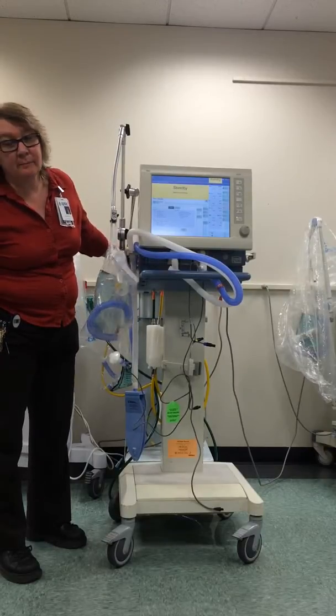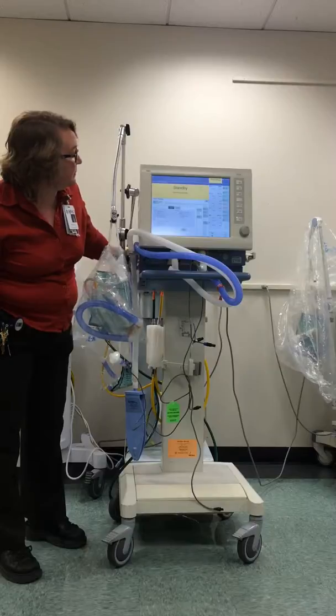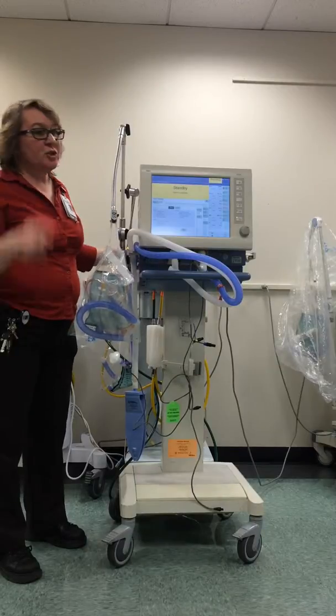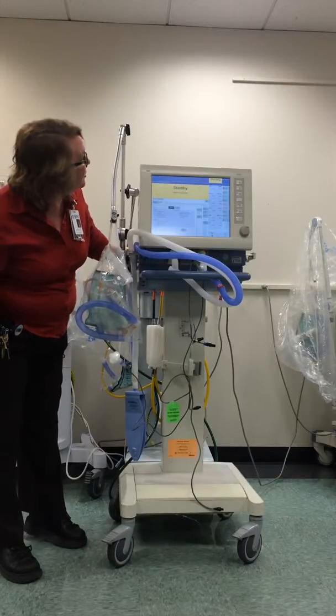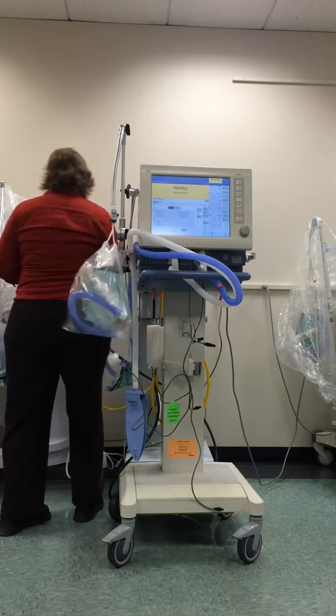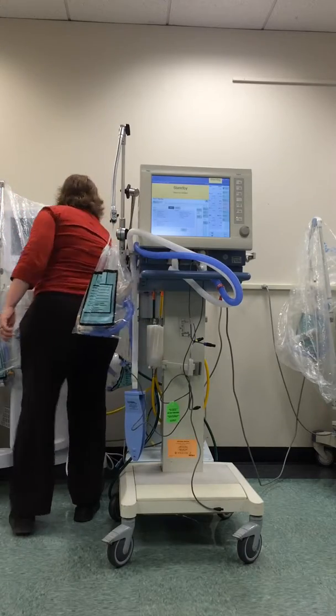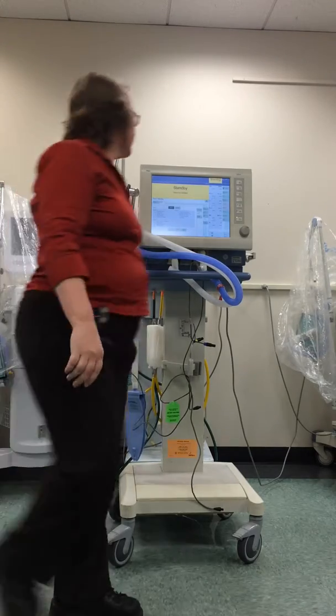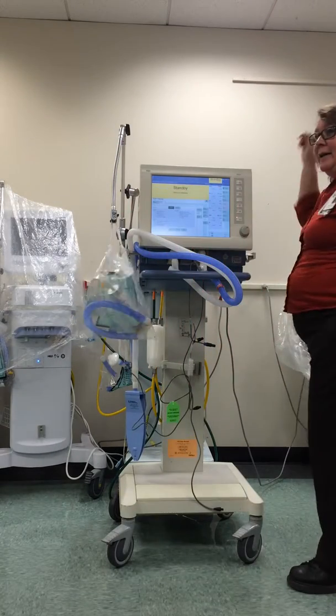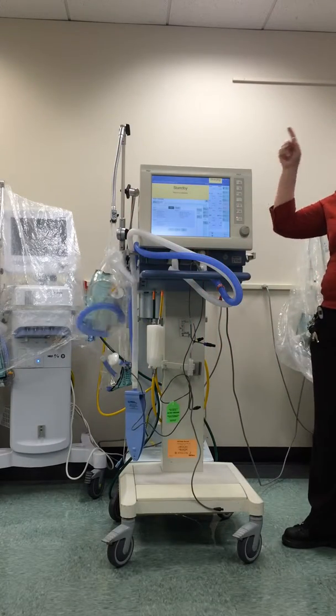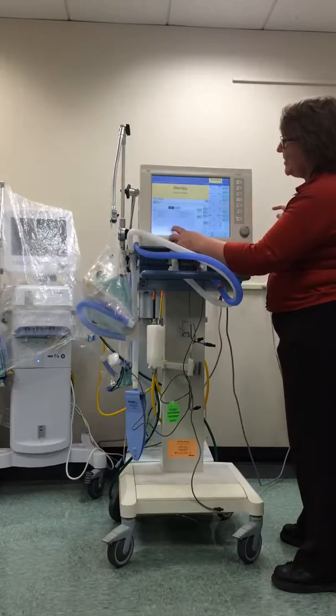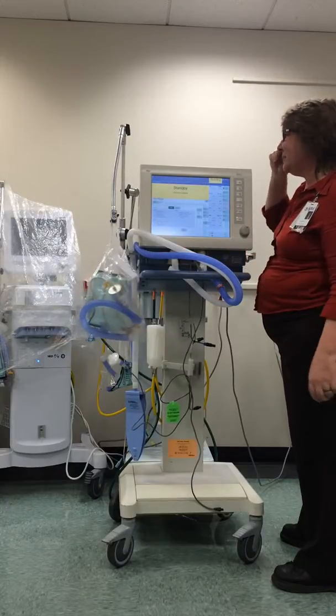Check is active, please wait. Same thing it says in between them all. It's just making sure everything switches over the way it's supposed to. Connect air and oxygen. So those are now both in. Audible alarm sound. Yes, we can hear it. So hit yes. Just checking that it works.